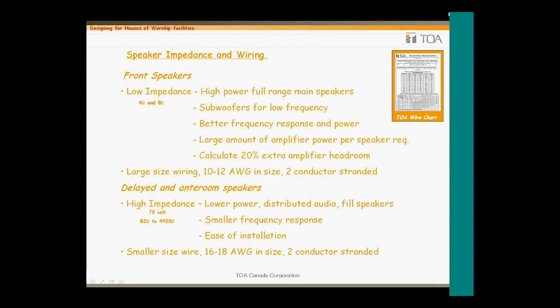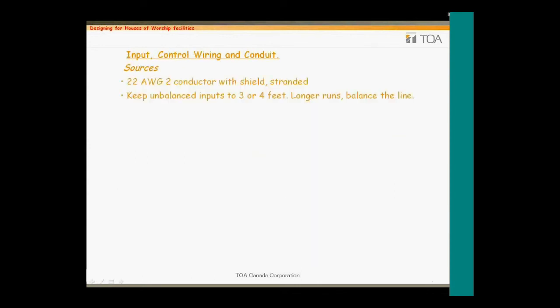Download the TOA wiring size chart on our website to help you determine the size of wiring required for the power being delivered to the speaker load. For input wiring of balanced audio lines such as microphones or line level feeds to amplifiers, use a two conductor stranded pair with shield of about 22 AWG gauge in size. One item that often generates calls is the installation of unbalanced lines from CD players, etc. These types of signal lines are only usable for a few feet in any commercial application. If you need to run these at any length, balance them up first using a suitable transformer or active device — failure to do so can lead to some nasty noise in the system.